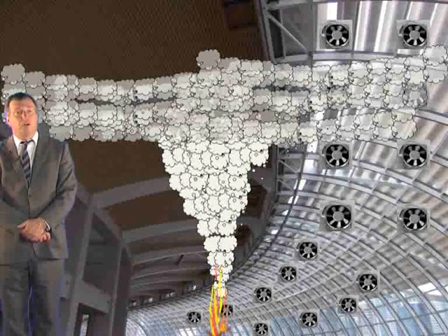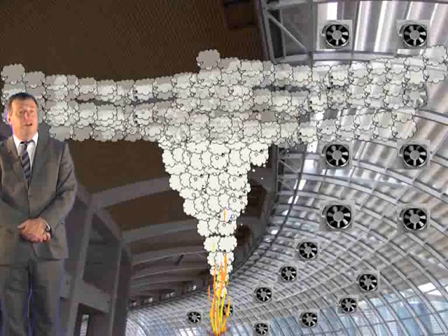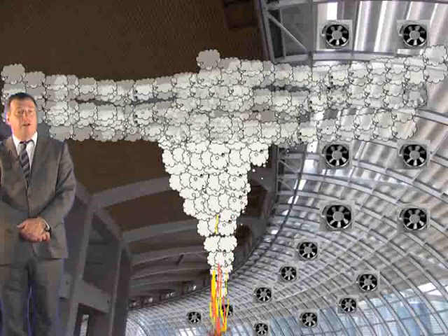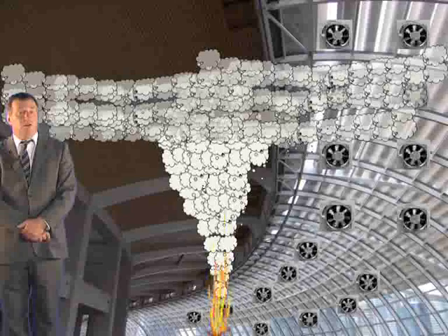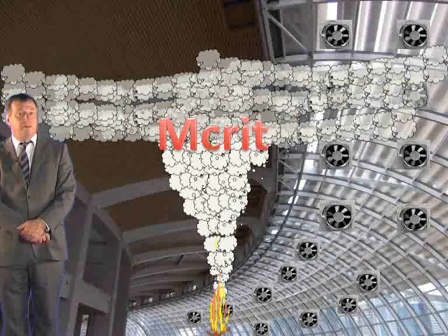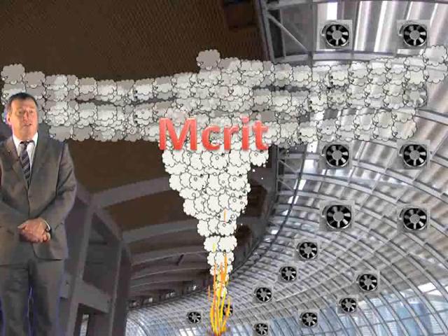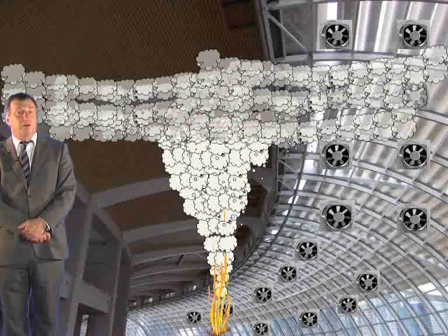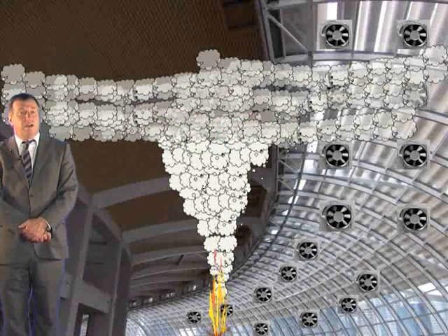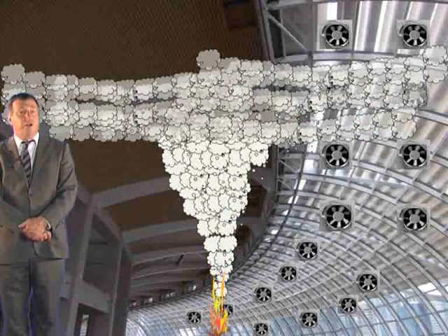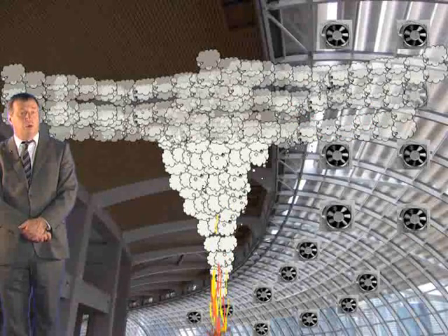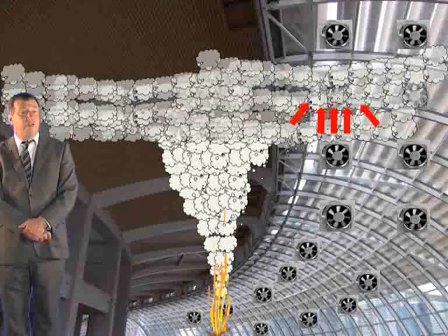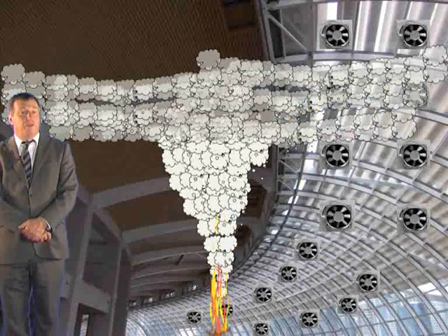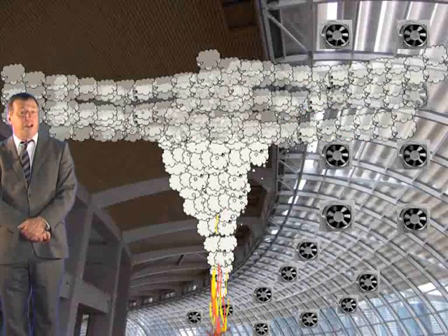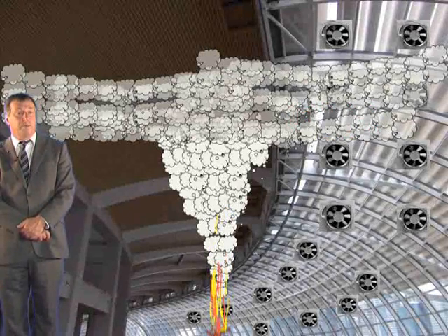The number of exhaust points within the reservoir is important, since for any specified layer depth there is a maximum rate, which is referred to as M crit, at which smoky gases can be allowed to enter any individual exhaust point. Any further increase in the rate of exhaust through that exhaust point will serve to draw air into the orifice from below the smoke layer, and this air will be in the form of a vortex, and this effect is often referred to as plug holing.